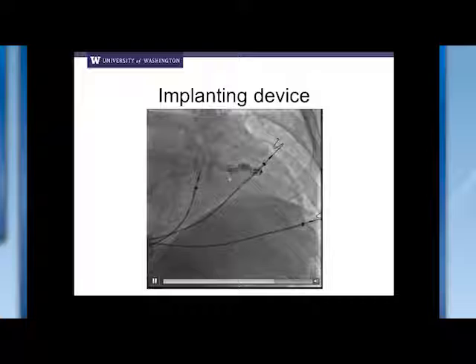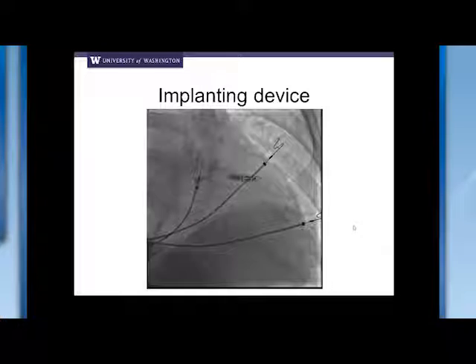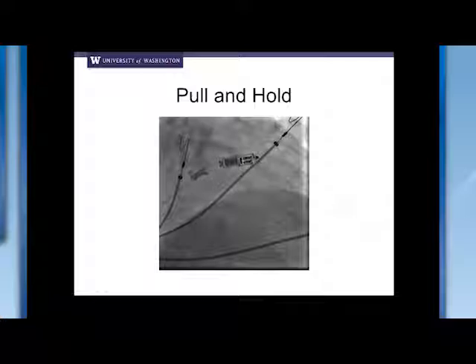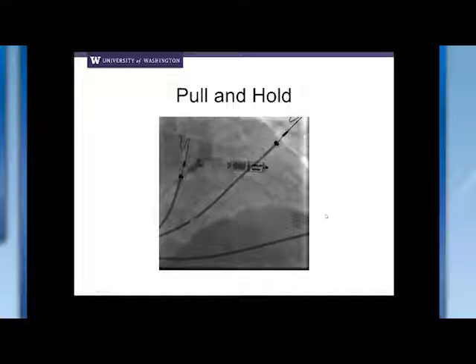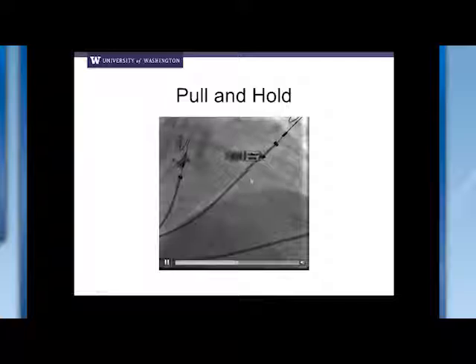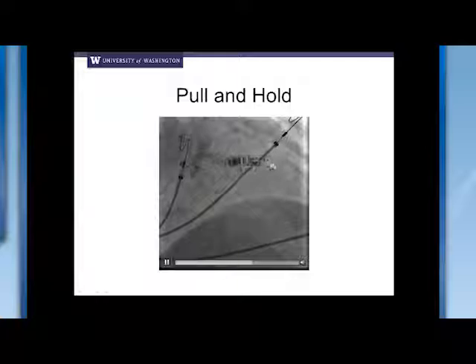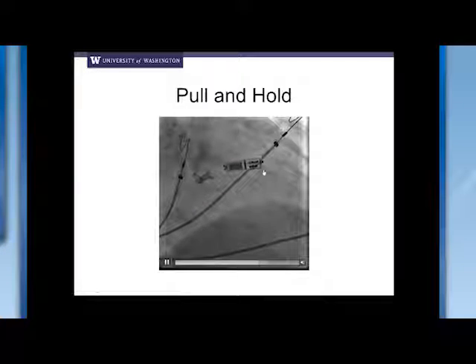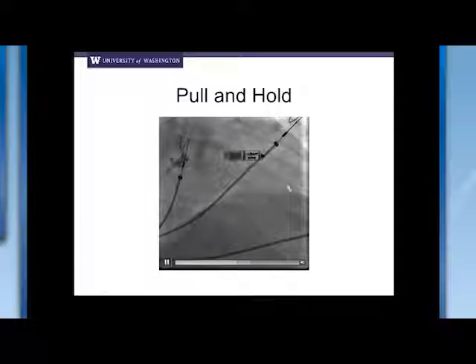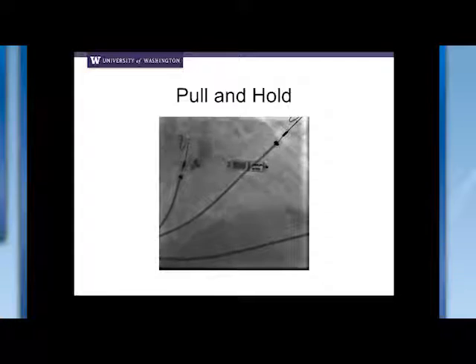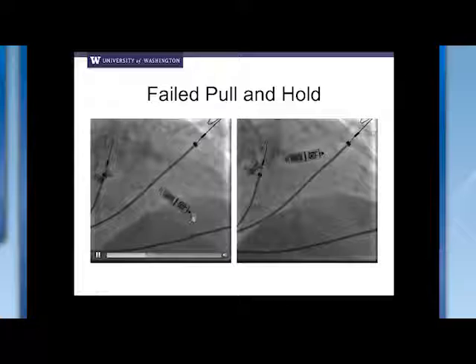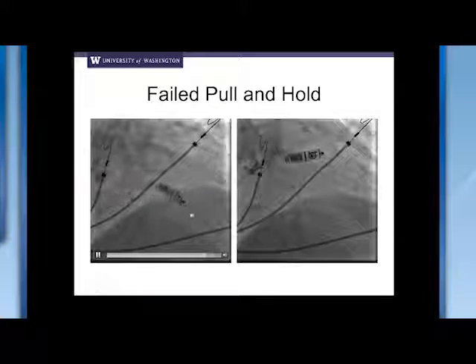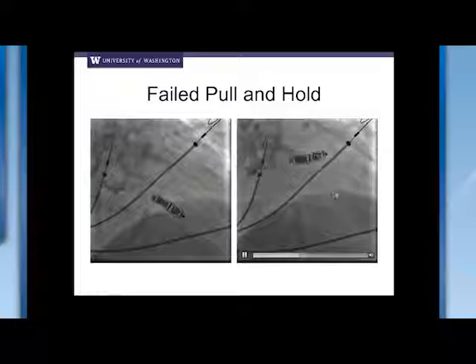And one of the interesting things is, once we do this, this device is now implanted and would be considered working. Now, one of the things that we do to make sure that we feel like this device is not going to dislodge is you do what's called a pull and hold test or a tug test, and you're looking, of these 4 tines that are here, do 2 of the 4 look like they are embedded in the myocardium? And here I'd say that one of these down below looks like it bends as I'm tugging on it, and then there's another one up top here that looks like it is embedded. As long as there are 2 of 4, the dislodgement rate in the studies has been 0, so you really feel comfortable if there are 2 of 4 implanted.